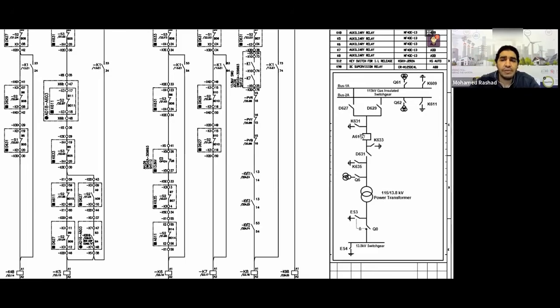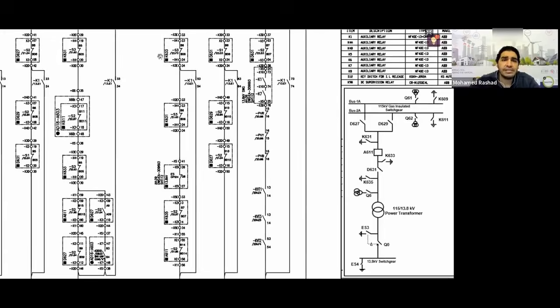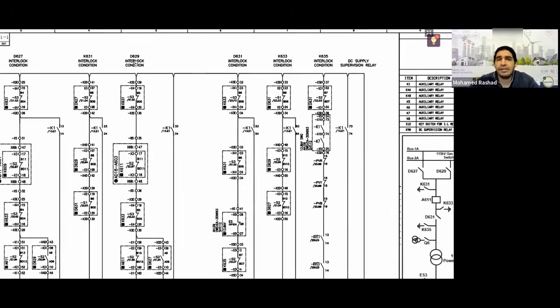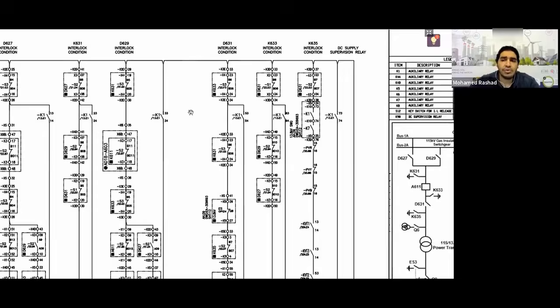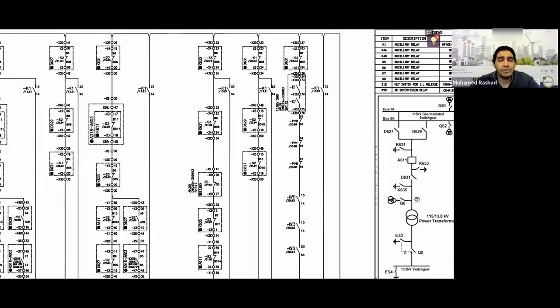So if I'm looking at the breaker, then my breaker, which is A611, should be open, right? And is there another breaker? Are there other grounds? Let's see together. He told you regarding D627 and D629. If he's checking on grounds, he told you, grounds before and after, right? Who are the grounds before? K633 and K631, assuming the breaker is not an isolation point. And who are the grounds after? K635. And there are grounds on the other side after the transformer, which is ES3, right?